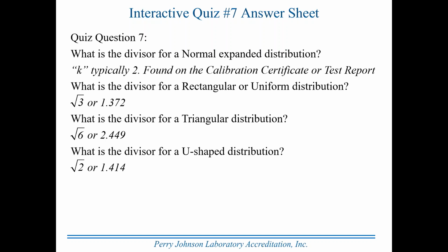Now there are a number of other distribution types, but these are the ones you're going to encounter most often. And for instance, the U-shaped distribution is encountered in laboratories that use what's called a boundary-driven heating and cooling system, where as the temperature drops down to the low limit of the acceptable range, the heat is turned on, driving it back up. And when it starts to approach the upper limit of the acceptable temperature range, the air comes on and forces it back down. So it's a constant battle between the high and low, and it's pushed all the way to the low extreme before the heat comes on.